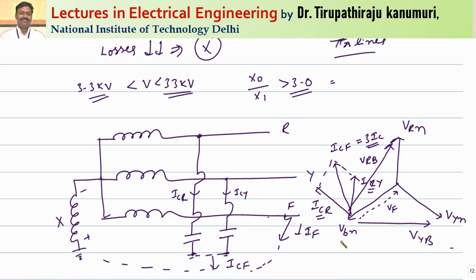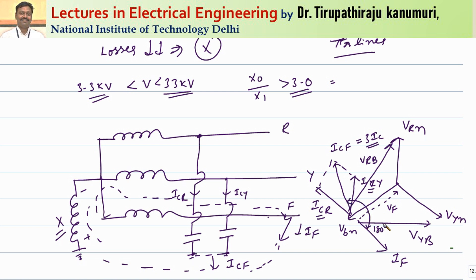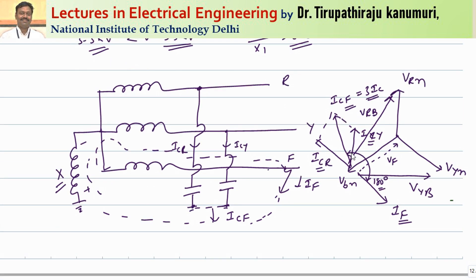Because the system is more reactive and very less resistive, the fault current IF automatically lags nearly by 90 degrees — generally between 80 and 90 degrees, approximated as 90 degrees. This fault current makes a 180-degree phase shift with respect to ICF, so it automatically nullifies the capacitor currents. When capacitor currents are nullified, the effect of arcing grounds is completely eliminated. Since it is purely reactive, no resistive component is needed — that is the first advantage.